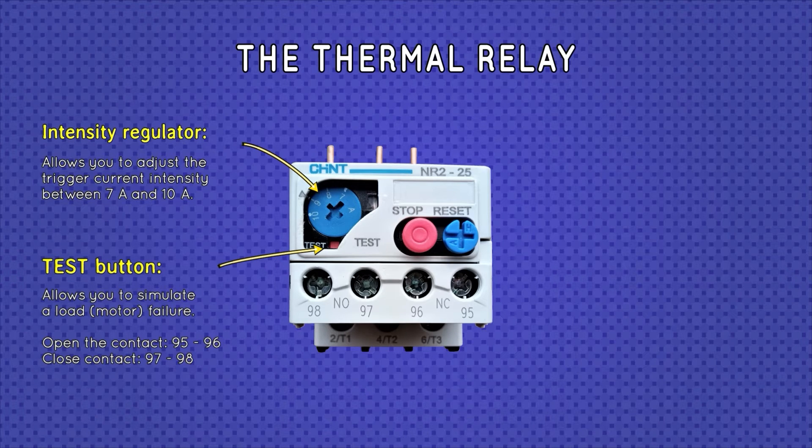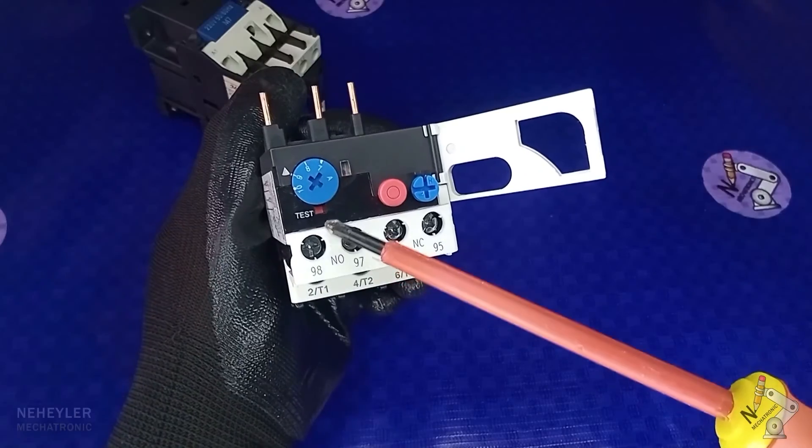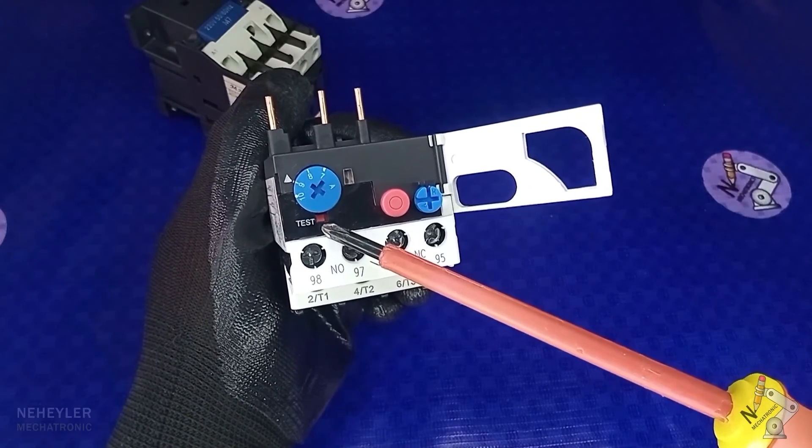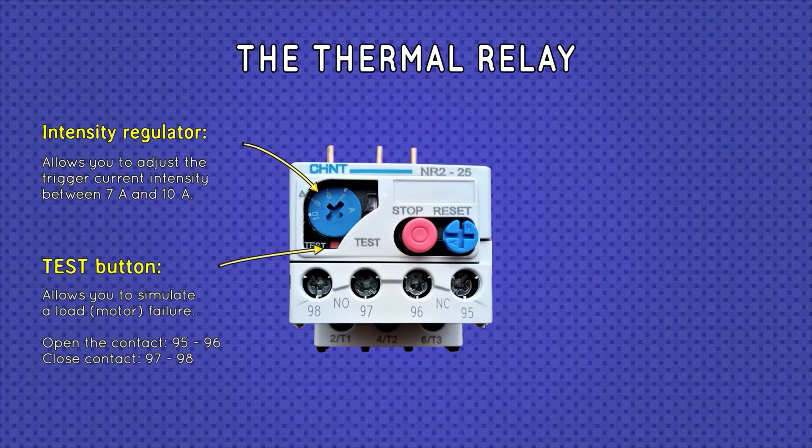The test button, which allows us to simulate an engine failure. In this model we have it here below the dimmer switch. If this test button is pressed, then what it does is it opens the normally closed contact 95, 96 and closes the normally opened contact 97, 98. And these will remain in that state.